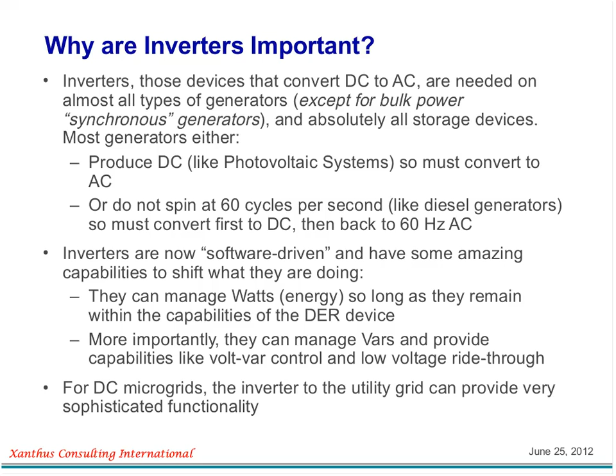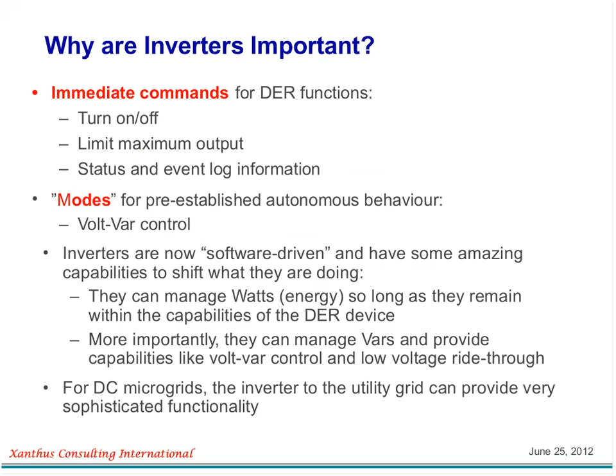So this is really important - inverters are software driven. You can tell an inverter to do an awful lot of things you didn't think it could do. Instead of being a dumb machine that just does what its hardware does, you can program the inverter to do a lot of things - change voltage levels, change VAR output, even have algorithms to figure out exactly what level it's going to go to. This is really a critical point.